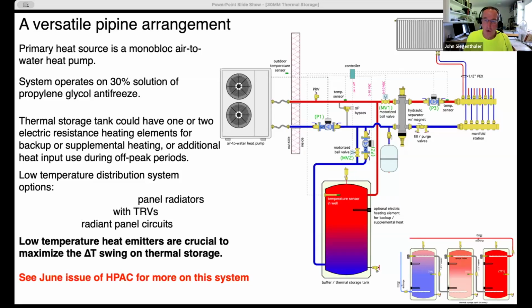And then there is another mode where the heat pump would be off and we would turn on circulator P2. We'd control the speed of circulator P2 and we'd be sending cool water coming back from the panel radiators into the lower portion of the tank. Hot water comes out the top, goes through MV1, through the hydraulic separator and out to the load. So there's basically three modes: heat pump direct to the heat emitters, heat pump to storage, and storage to the load. And that can all be controlled, depending on what the rate structures are.